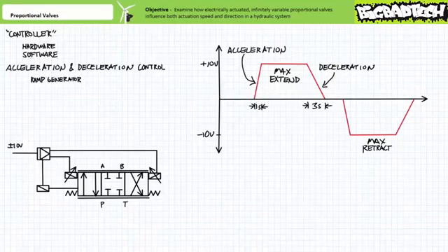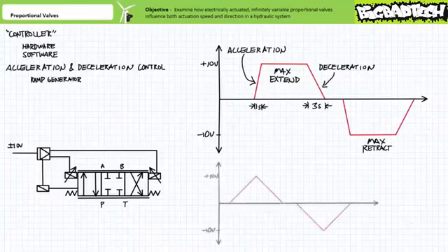It exhibits similar acceleration and deceleration in the retraction direction. Note the flat line periods between acceleration and deceleration periods is when the actuator is experiencing maximum flow and moving at maximum speed in a given direction.